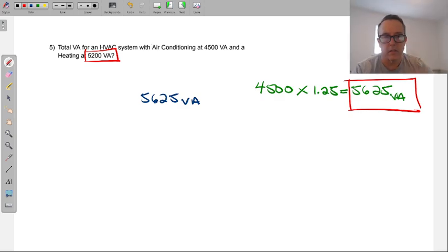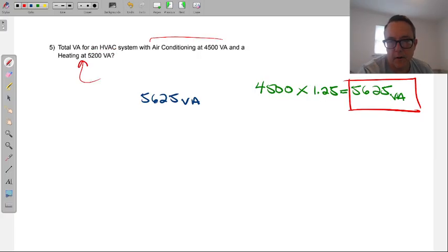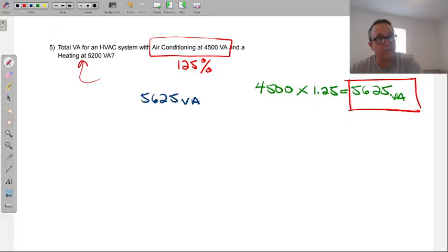Well, the code section says if the heater is the bigger one, then we have to first increase the air conditioning load by 125% and see where that lands now. It could still be smaller. And then if it's still smaller, then we still go with the heater.